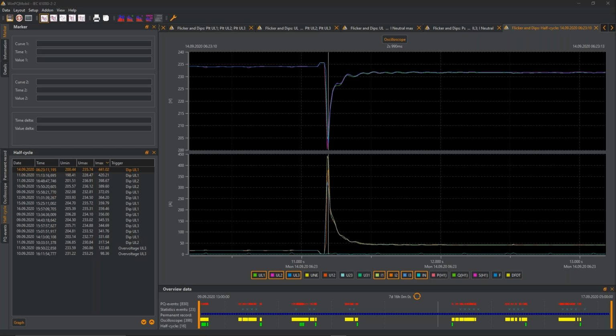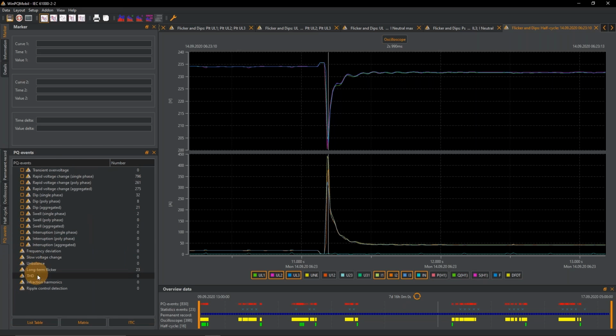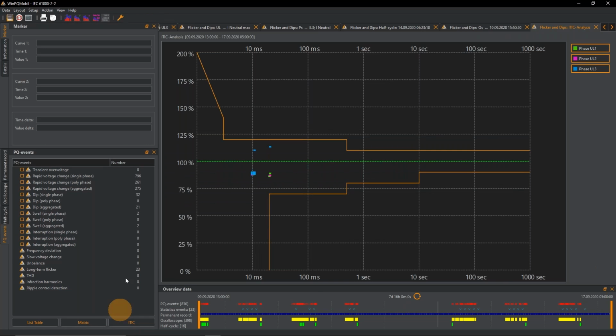And now I'm going to show you the third way to have a look at the dips and swells, the events in here. If I click on power quality events over here, there's an ITIC or a CBEMA curve. If I click on that, I get the very well-known ITIC curve, and I can see some dips over here, but also some swells. So they're all linked. If I hover there with my mouse, it gets a little bit bigger. And if I click there, it opens the fault record.